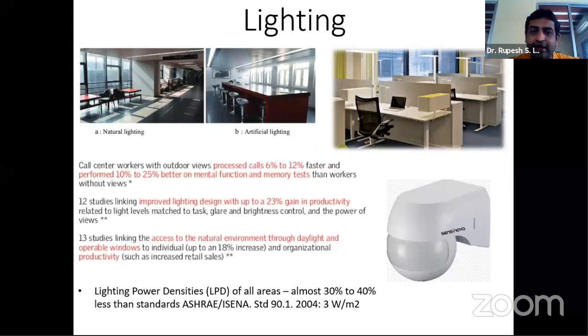And coming to the lighting, of course, there are different ways of doing it. One is the classical lighting, which we would provide in our everyday overhead or false ceiling. A zero energy building or a highly efficient building could go in for a concept called task lighting. Now, the advantage with task lighting is that only the occupied task area is lit.